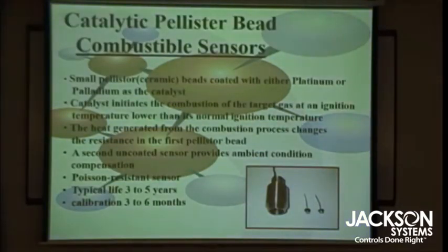Catalytic bead sensor, similar. In this one we have a reference bead and an active bead, and basically the active bead is covered with platinum, like you find in catalytic converters in vehicles. When it's heated and comes in contact with combustible gas, it burns and it changes the resistance of the unit. It's compared to the reference bead, which has no coating on it, and that change is proportional to your gas concentration. They respond very, very quickly, but if you have a lot of gas, they require frequent calibration.